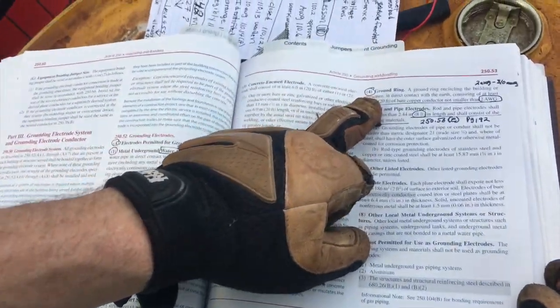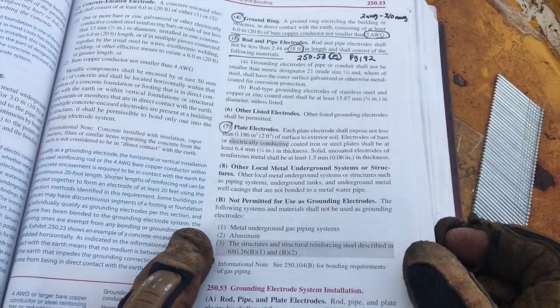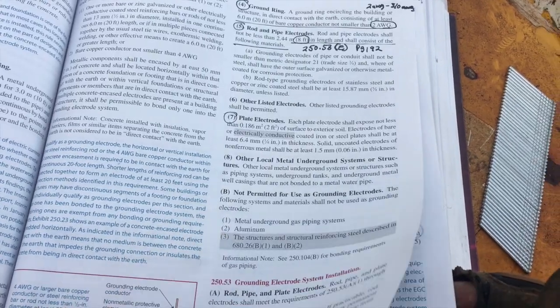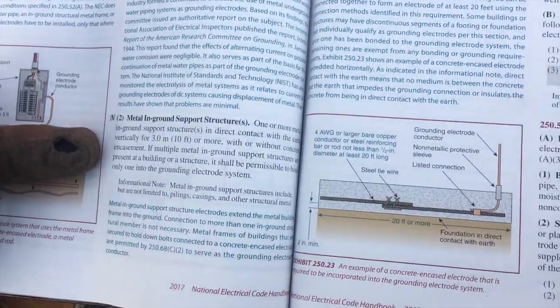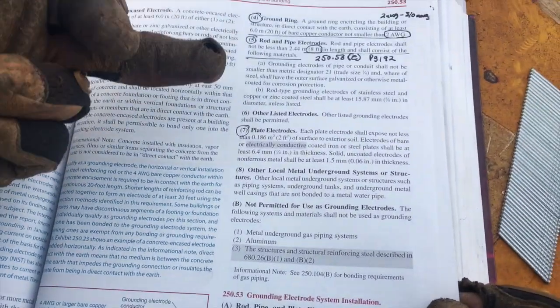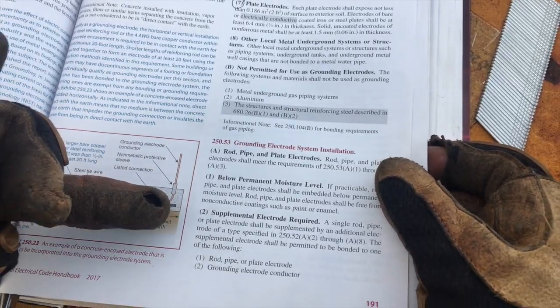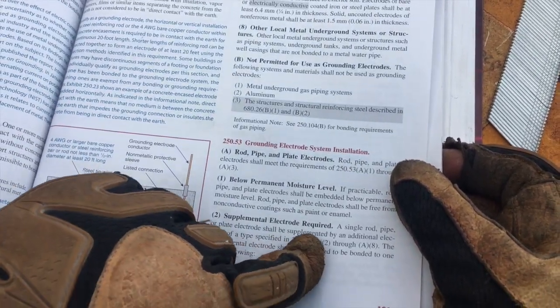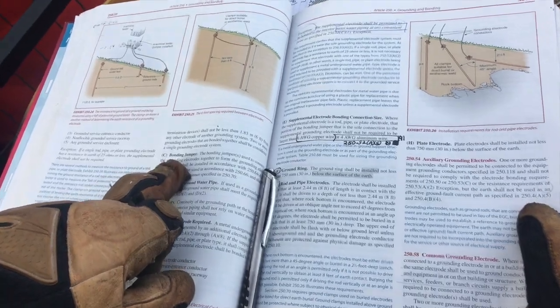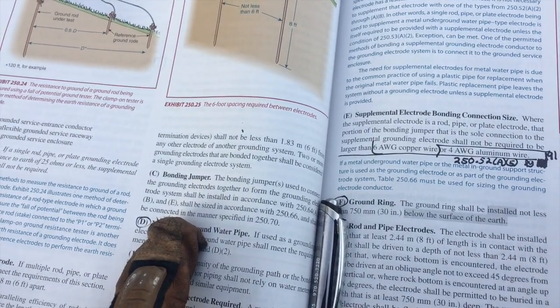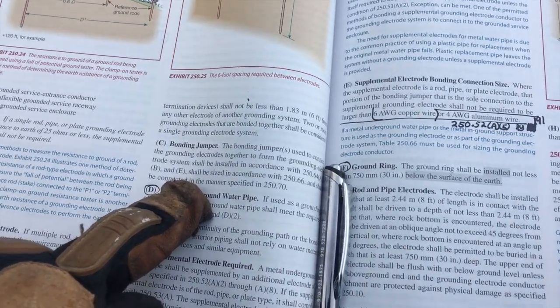Your bonding jumper will be discussed. Also you could create a ground ring, that might have been a good idea around that whole structure. Again, they're going to move that, so I don't know how permanently that's going to be, but at least I have a 10 foot ground rod. And 250.52 it will be talking about your water pipe, your metal and grounded support structure, ground ring, rod, plate. And then in 250.53, your rod permanently installed, supplementing electrode conductor. Maybe I should add two ground rods driven for that. You could still do that. But bonding jumper right here is where we were talking about that neutral and ground bonding at the first point of disconnect. Again, the generator portable has its own disconnect right then and there shutting off.